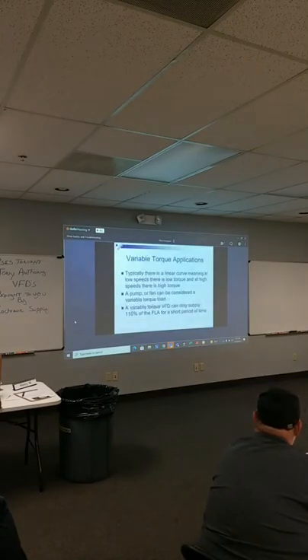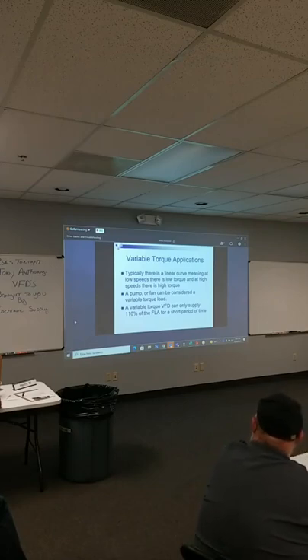And that's what we're talking about. Most variable torque drives, because once again it takes almost no torque, are 110% for 60 seconds. So it takes almost no torque to get that drive running. Whereas a constant torque drive actually has 150% overload capability for 60 seconds, because you've got to have a lot of torque at low speed.